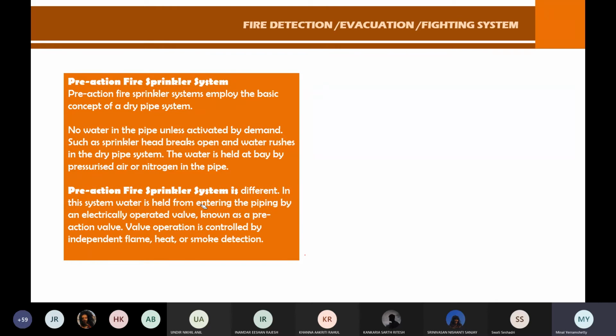So that means, unless activated by demand — such as a sprinkler head breaking open and water rushing into the dry pipe system — until then the system remains dry. Do you understand what I said? The water is held at bay by pressurized air or nitrogen in the pipe.